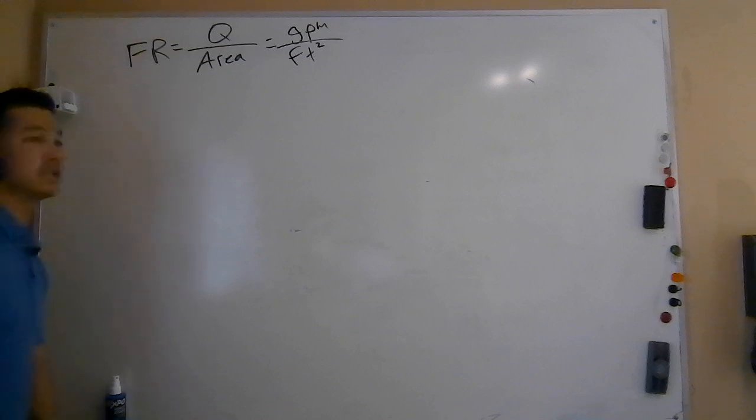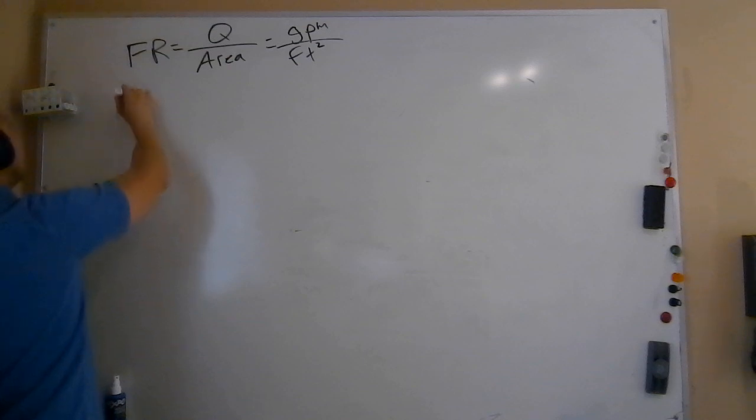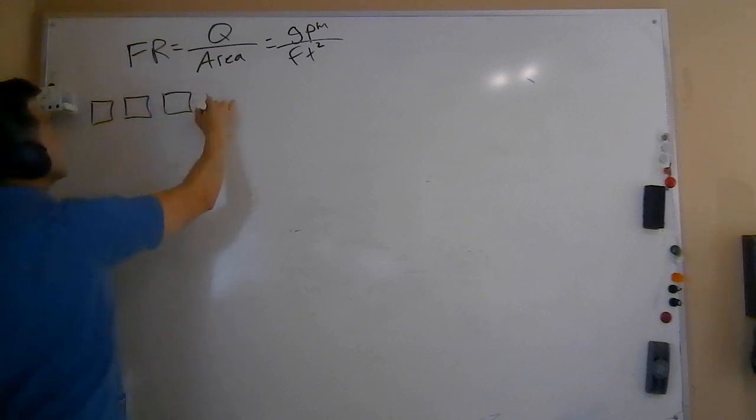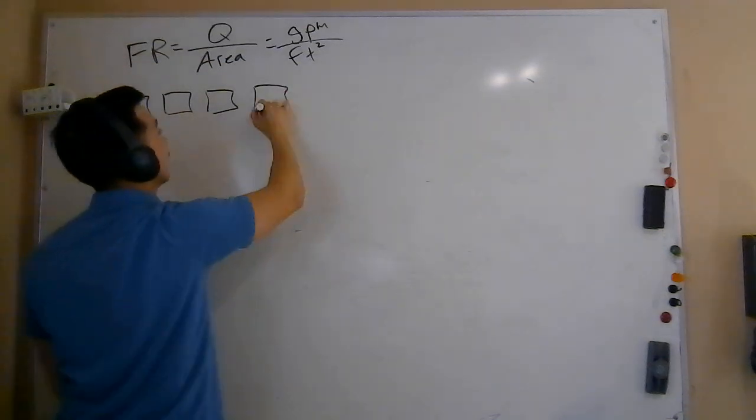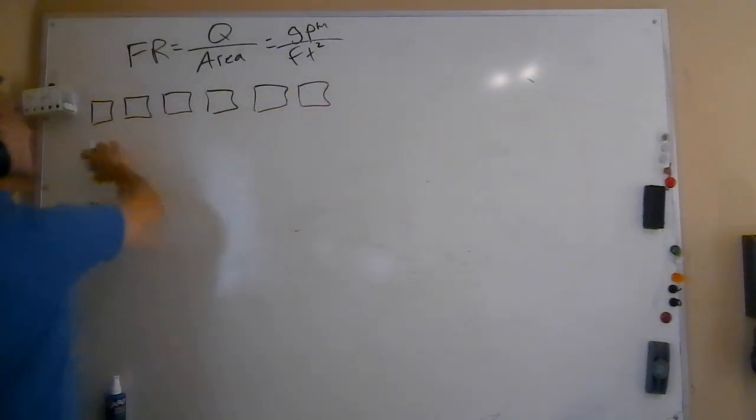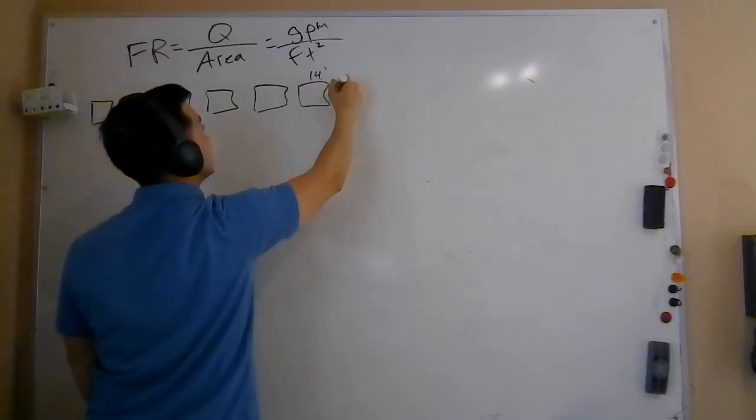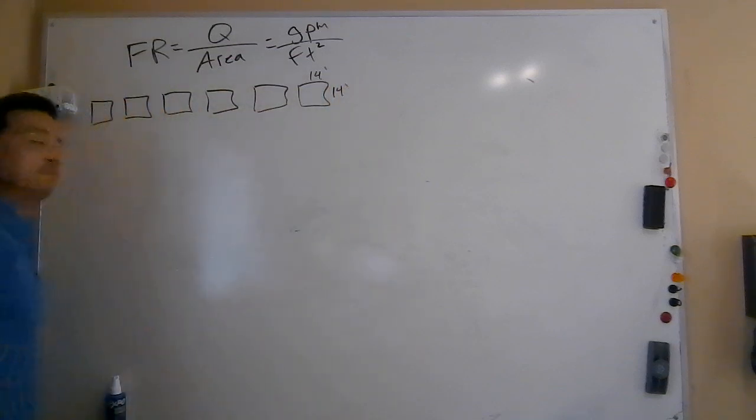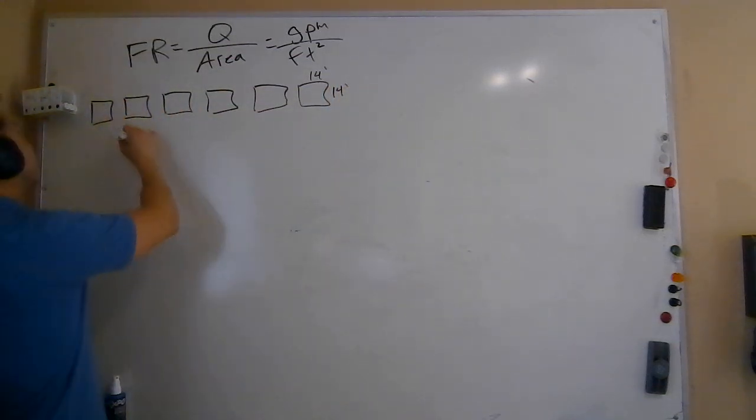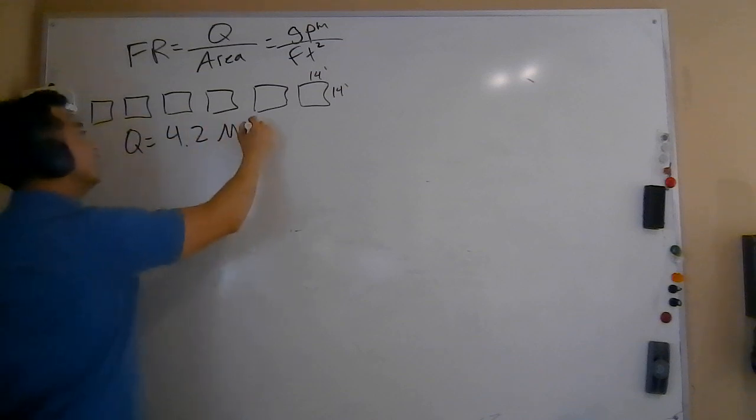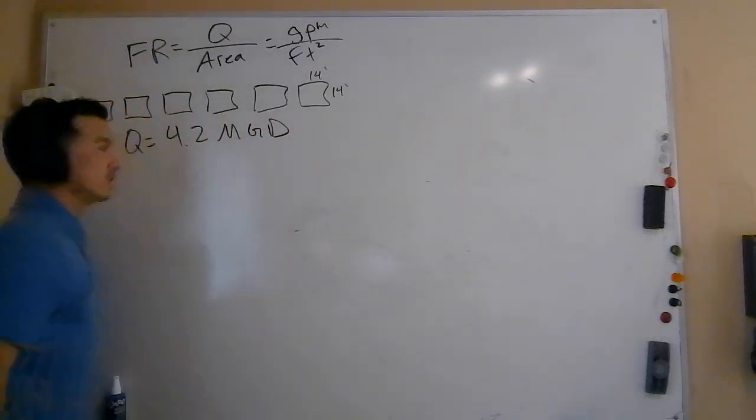In this example problem, we're going to be looking at a wastewater treatment facility located close to Palomar College, the Meadowlark reclamation facility. At this facility, they have six identical size filters that they use. These are carbon-based filters. They've each got the dimension of 14 feet by 14 feet. And the average flow that we are treating right now, we're going to say 4.2 MGD. Remember what MGD stands for? Million gallons per day.